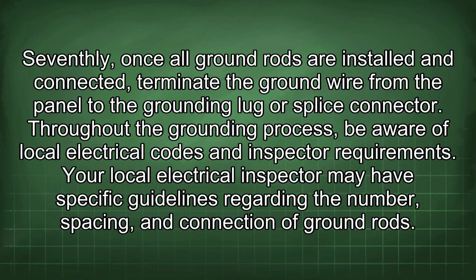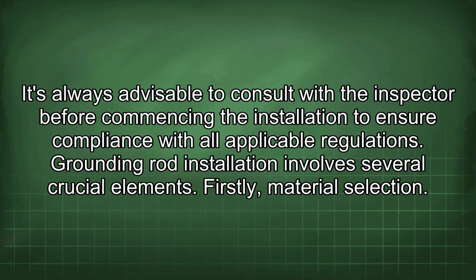Seventhly, once all ground rods are installed and connected, terminate the ground wire from the panel to the grounding lug or splice connector. Throughout the grounding process, be aware of local electrical codes and inspector requirements. Your local electrical inspector may have specific guidelines regarding the number, spacing, and connection of ground rods. It's always advisable to consult with the inspector before commencing the installation to ensure compliance with all applicable regulations.